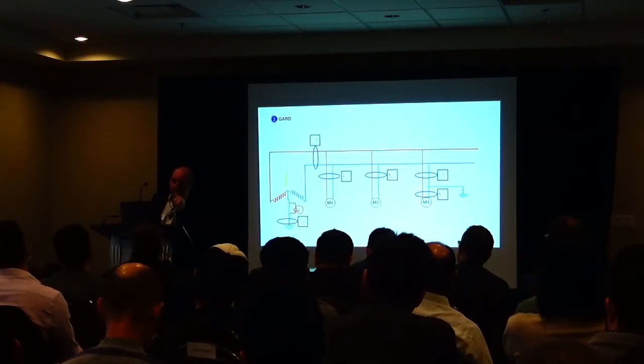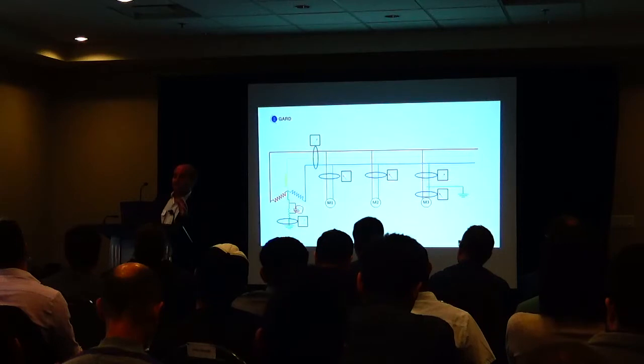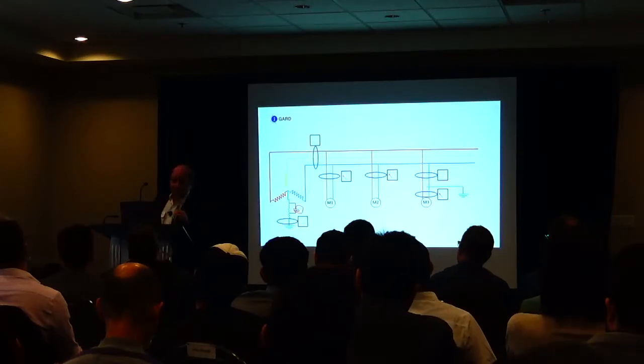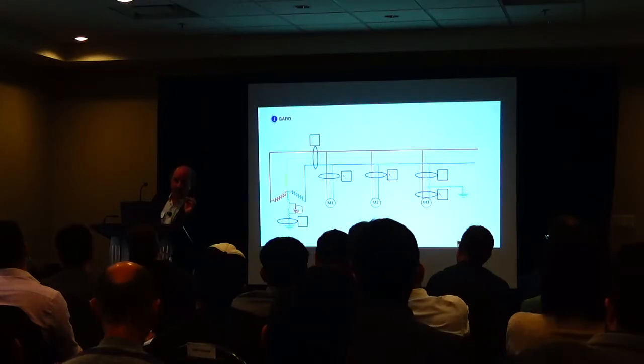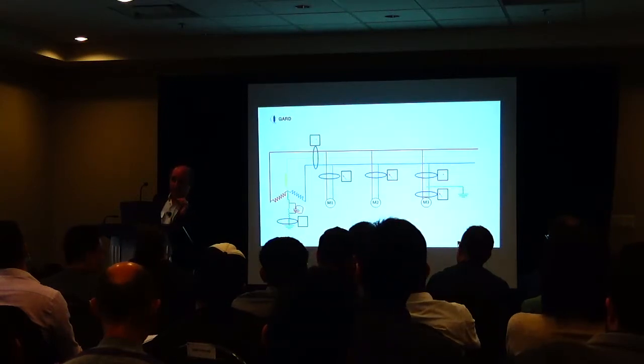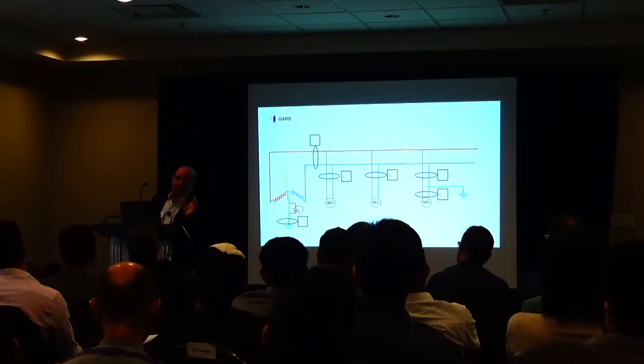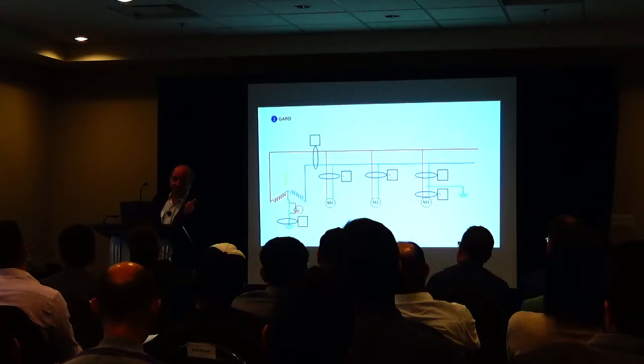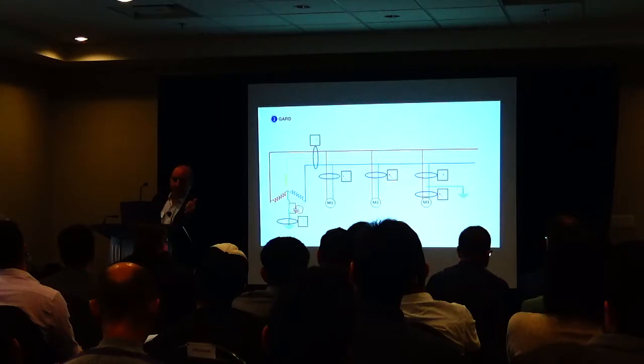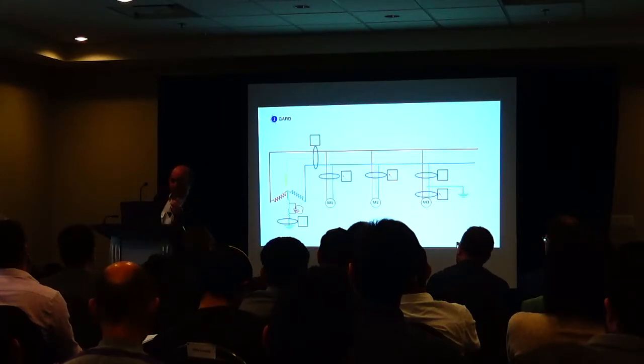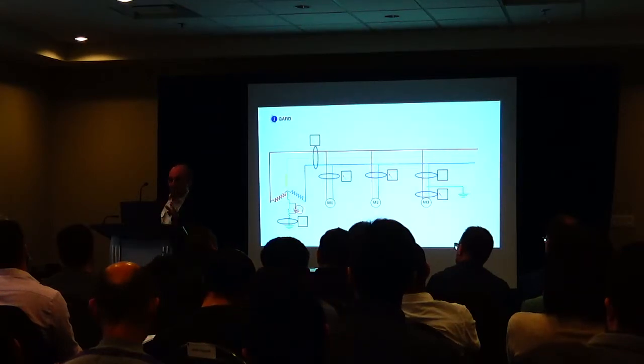Yeah, that's what you would have to do. Oddly enough, and I wasn't going to mention this, in Canada you are allowed to have a resistance grounded system with a distributed neutral. I don't agree with it, but you're allowed to have it. The rules are different. You have to trip instantaneously if you have a ground fault. So you don't get the benefits of having a resistance grounded system because you have to trip immediately if you have a ground fault. But I don't like it specifically because I think it's dangerous.